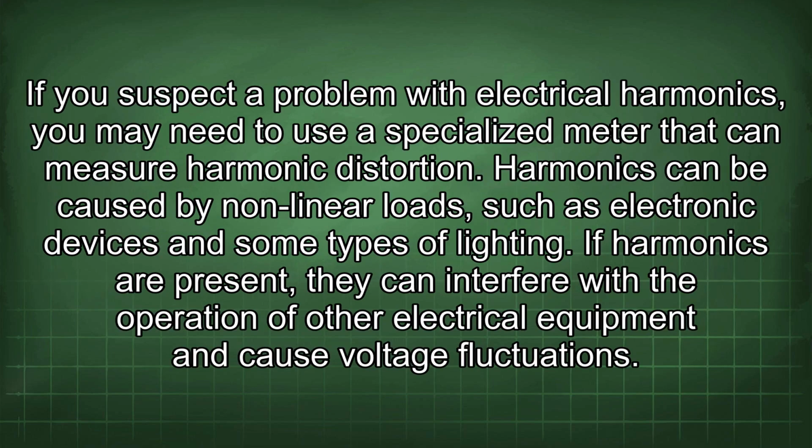If you suspect a problem with electrical harmonics, you may need to use a specialized meter that can measure harmonic distortion. Harmonics can be caused by nonlinear loads, such as electronic devices and some types of lighting. If harmonics are present, they can interfere with the operation of other electrical equipment and cause voltage fluctuations.